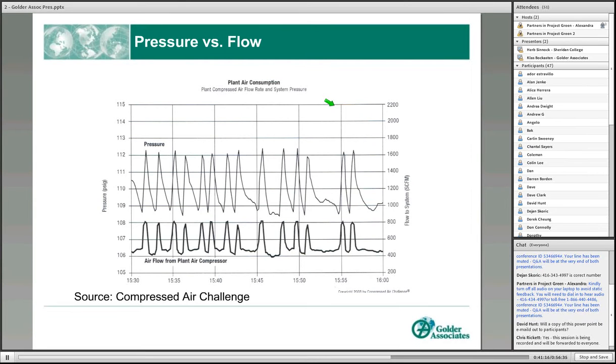By having a compressed air flow metering device outside of the compressor room, knowing what the flow is at any point, that's a great tool to analyze the system. And pressure is something you could follow on the master pressure gauge. In this case, you see a variation of roughly 3 psig. As I indicated before, if you have a flow pressure control device and a good control system that manages these 3 compressors, you should be able to bring down the pressure variation to between 1 and 2 psi, which will bring good financial return.